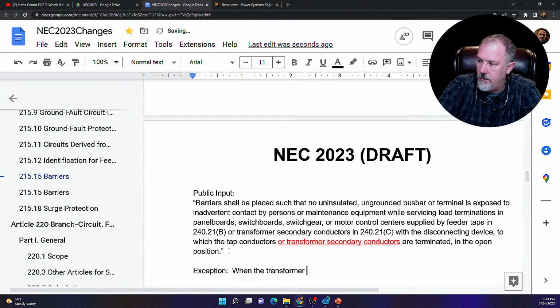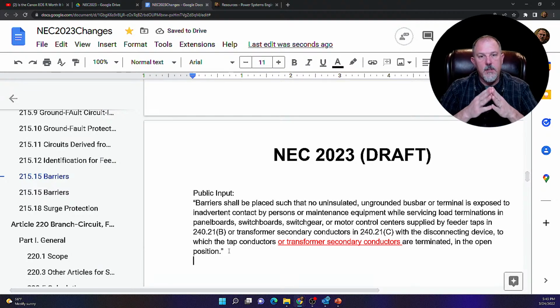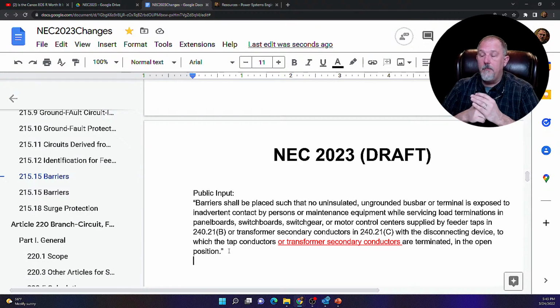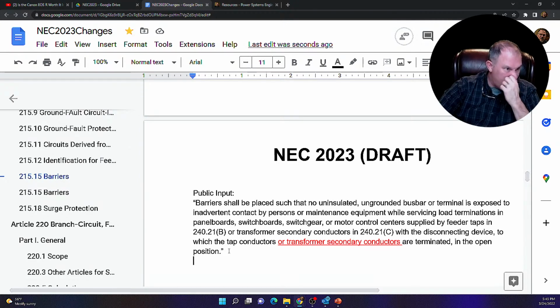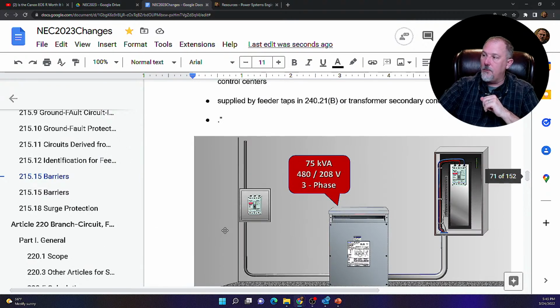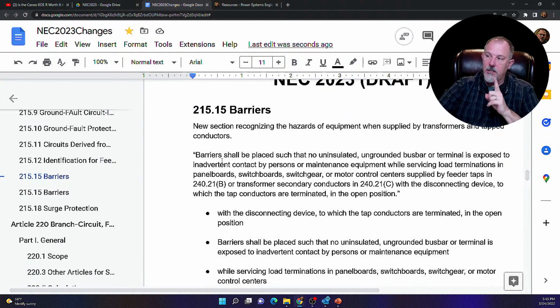When the transformer has an integrated overcurrent protective device, no, I don't need that exception. Because if I have a transformer that has a built-in overcurrent protective device on the secondary of the transformer, that is no longer a transformer secondary conductor, that's a feeder. So that would not require barriers because I have a feeder. All right, I'm liking it. So hopefully that helps you understand what this language means in 215.15.